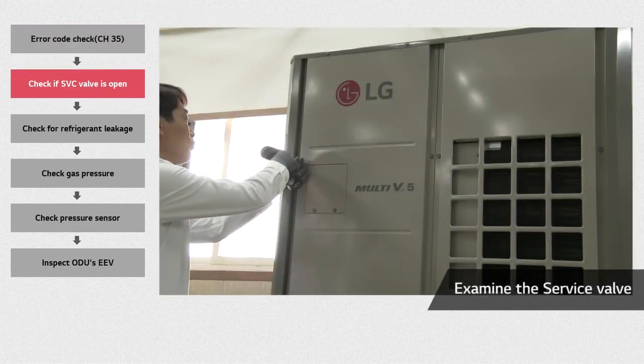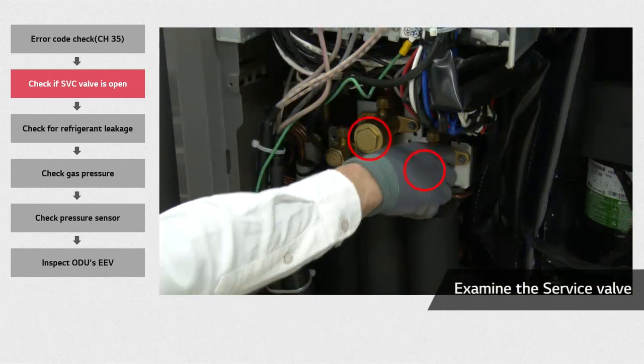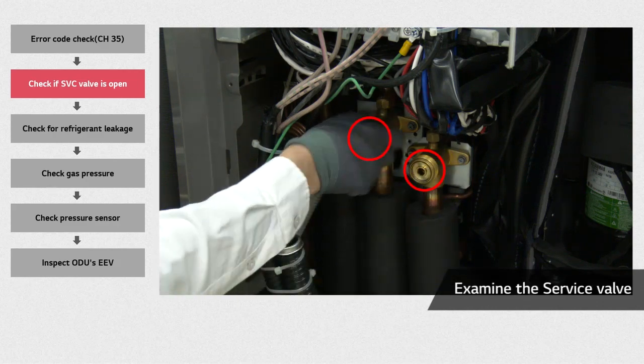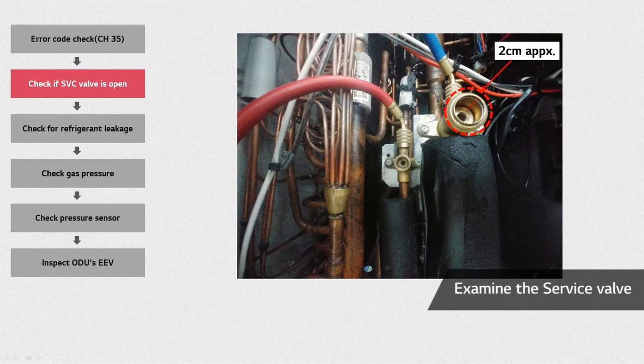To solve this error, start by removing the front panel of the outdoor unit. Remove the service valve cap to check if the valve is open or closed — it should be open. You can tell whether the valve is closed or open depending on the position of the top ring relative to the pipe. If the ring is about 2 cm inside the pipe, you can assume it to be closed. If it is almost parallel with the surface, the valve will be open.